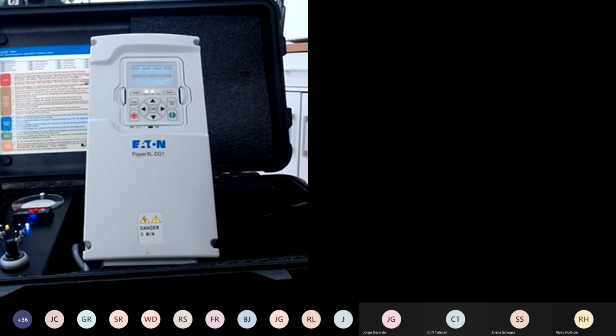When you have a drive, you have a 3-phase power going in, 3-phase power going out. Your VFD is sensing all that voltage, current. It can gather that data. So if you have a PLC or control system, you are actually gathering all those values, and you can use that, again, for an Excel spreadsheet, look at how your drive is performing. If it faults, be able to analyze a fault correctly. The drives do have overcurrent, over amperage, maybe a loss of a belt.